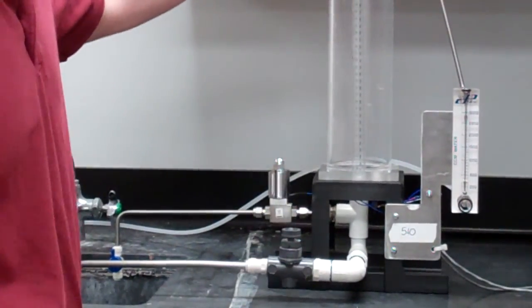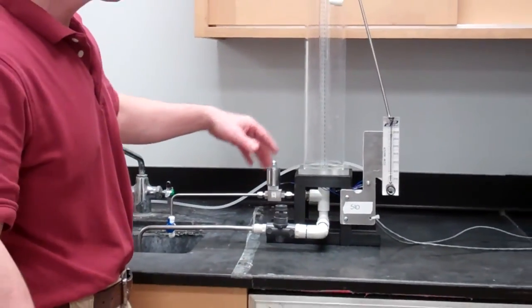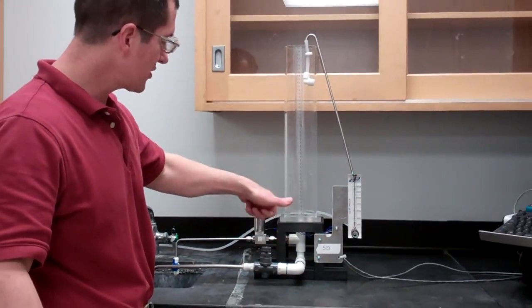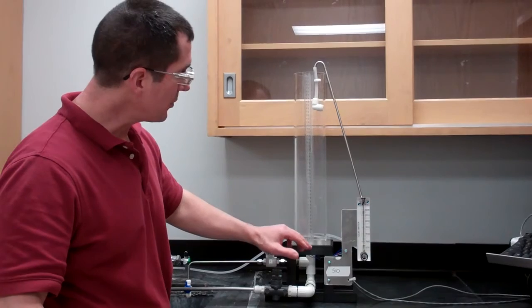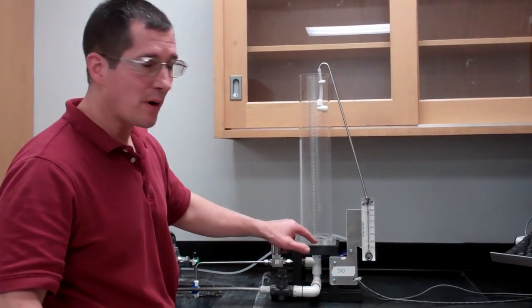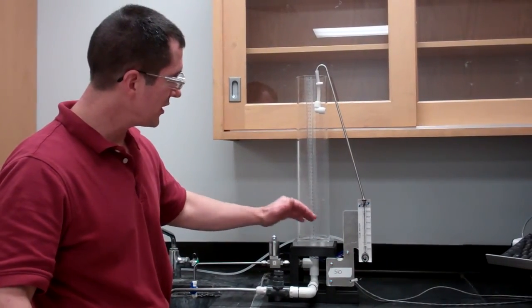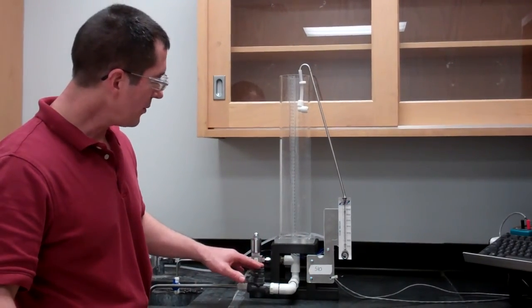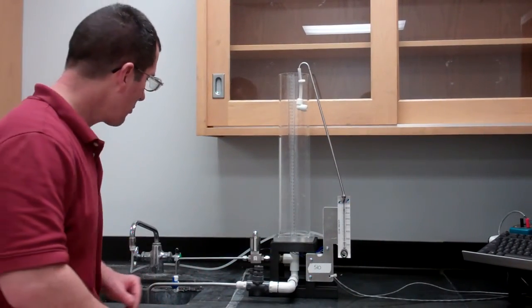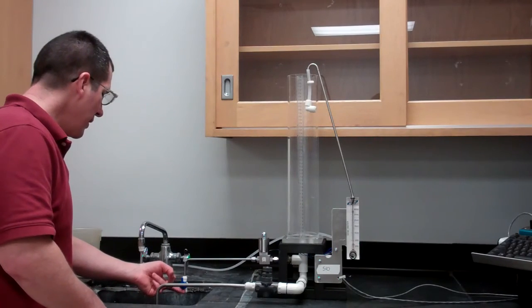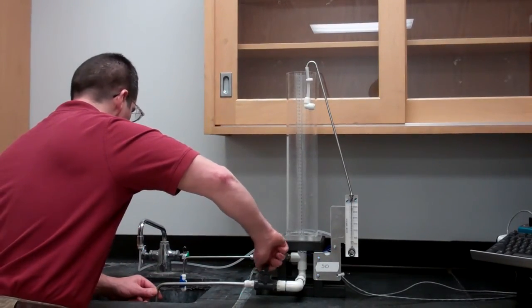So basically, if the level gets too high and you can't control it, you can drain some of the water out. Plus, when you're calibrating the pressure transducer on the bottom, you can also use that to drain some of the water out. So I'm going to go ahead and put some water in this tank. Right now I've got this valve open. Go ahead and close this valve here.